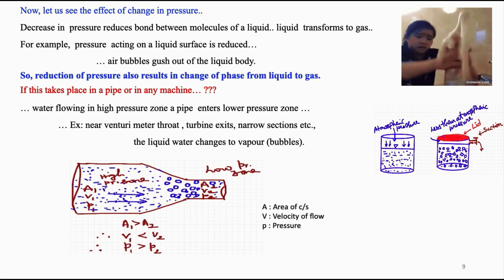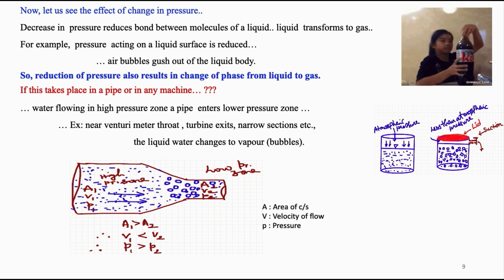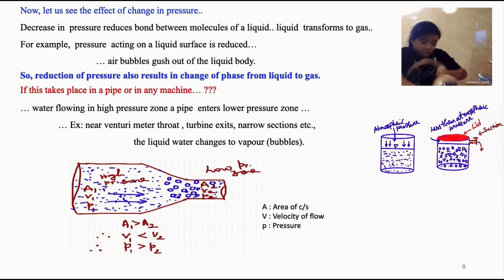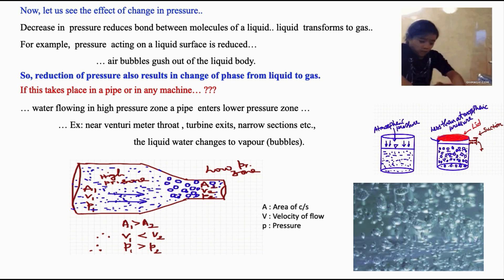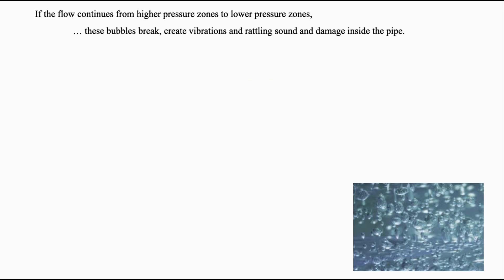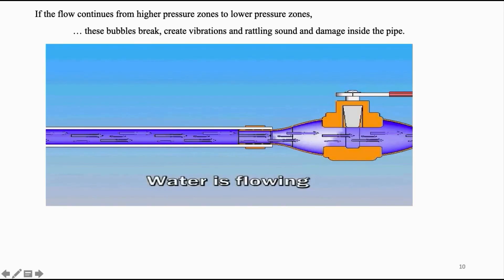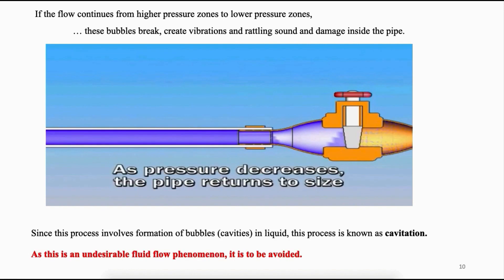As shown in the figure, flow takes place from a higher pressure zone to a lower pressure zone — best examples are flow through the throat of a venturimeter or flow at the exit of turbines and narrow sections. Here, water in liquid state gets transformed into gaseous state. Since the density of air is less than that of water, the volume abnormally increases once liquid becomes gas. As flow continues from higher to lower pressure zone, these bubbles break, create vibrations, rattling sound, and damage the inside of the pipe material. Since this process involves formation of bubbles — that is, cavities — in liquid, it is known as cavitation. This is an undesirable phenomenon and must be avoided while designing pipe networks or hydraulic machines.